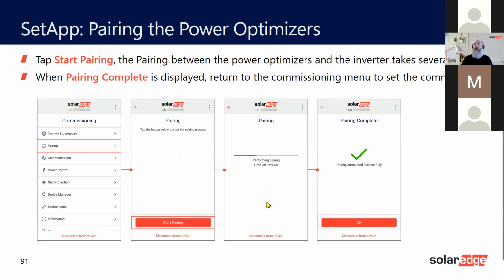Pairing of the optimizers. Well, we've already spoken about this. You know the three ways. One is with the inverter switch: hold it over 5 seconds from one position to the P position and release. If you hold that for over 5 seconds, it will pair. You can do the pairing in the SetApp, or you can do the pairing from the connection.